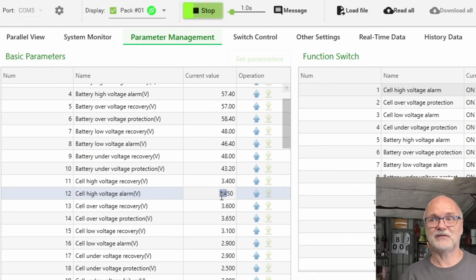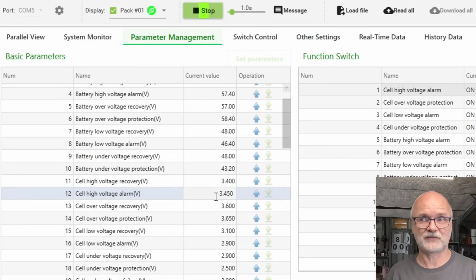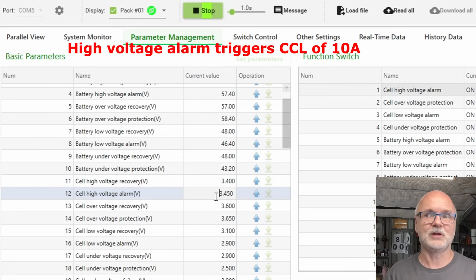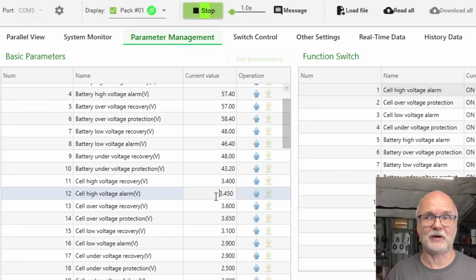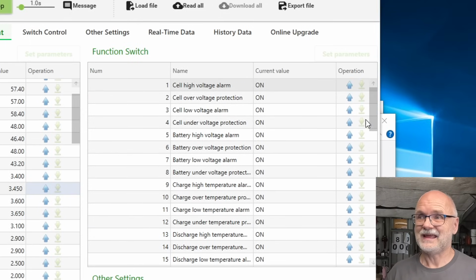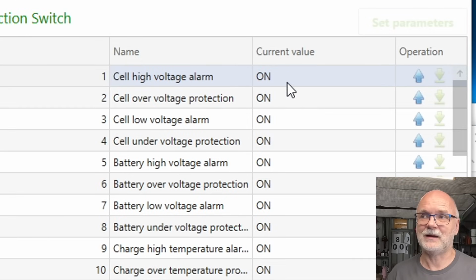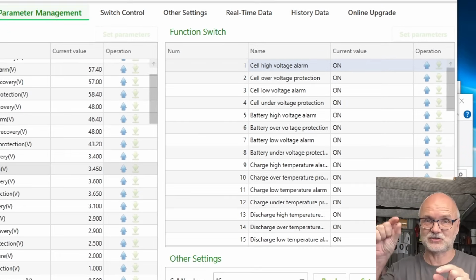But then as soon as one of the cells is over 3.43 volts and triggers the alarm, this BMS will report a CCL of 10 amps to your inverter. So it doesn't charge at full power anymore. So you could actually go into the switch functions and disable this cell high voltage alarm. See, this one is turned on by default. You only disable the alarm, not the protection, just the alarm. And then the BMS doesn't report 10 amps anymore and keeps charging full power until you hit the 3.45 volts. So you can actually make it work.